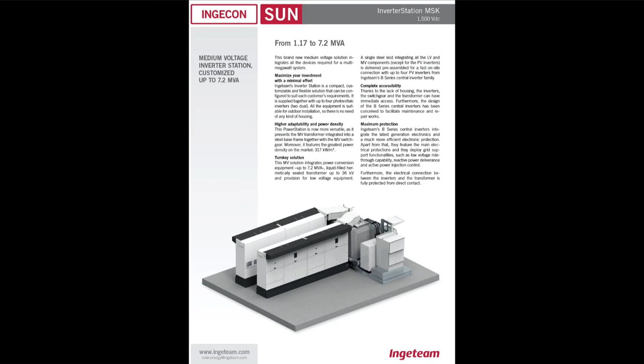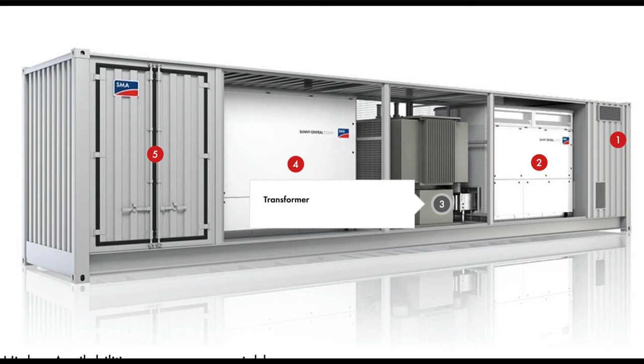Occasionally you hear about, in China they use stuff up to like 7 MVA. You're getting into really high fault current capabilities with those units, and that's problematic. You're getting really spread out too, even at 1500 volts those are massive arrays going into those transformers. I don't see the real benefit of it personally, but I can't say I've done 300 calculations on the subject and concluded it's clearly not cost effective. In the real world, 2 to 4 megawatts or MVA tends to be the size range most transformers are in for large plants.